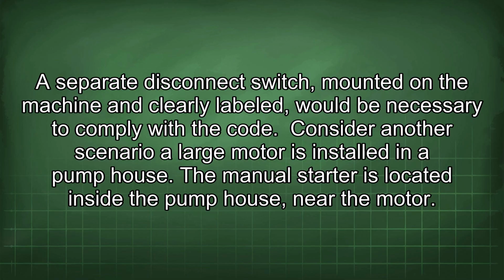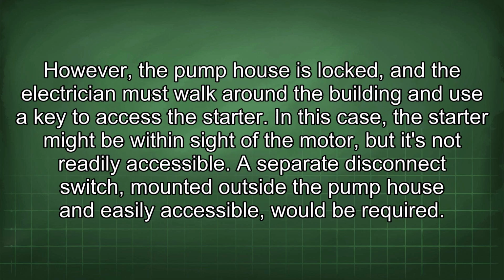Consider another scenario. A large motor is installed in a pump house. The manual starter is located inside the pump house, near the motor. However, the pump house is locked, and the electrician must walk around the building and use a key to access the starter. In this case, the starter might be within sight of the motor, but it's not readily accessible. A separate disconnect switch, mounted outside the pump house and easily accessible, would be required.